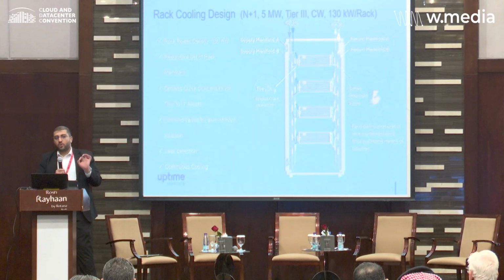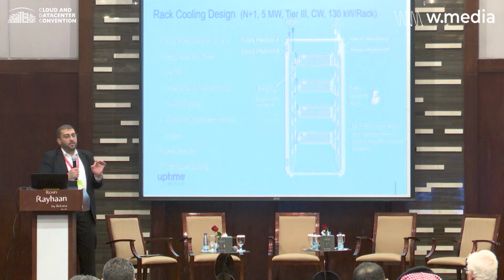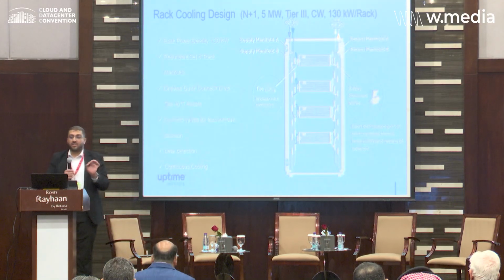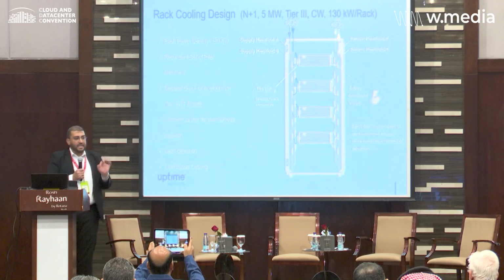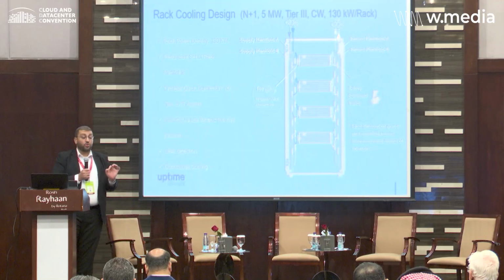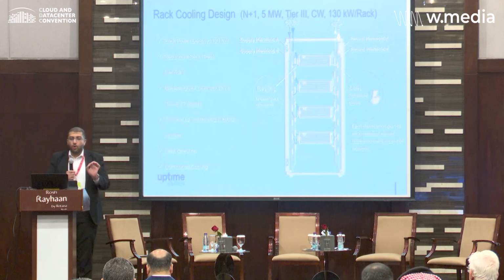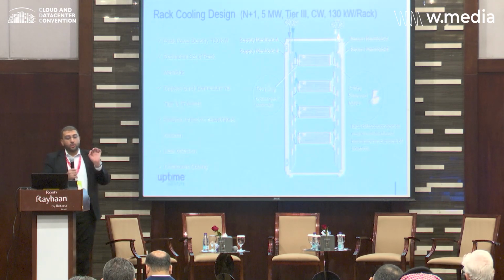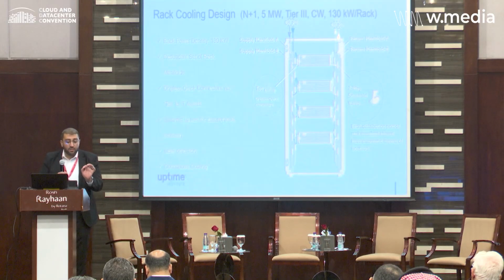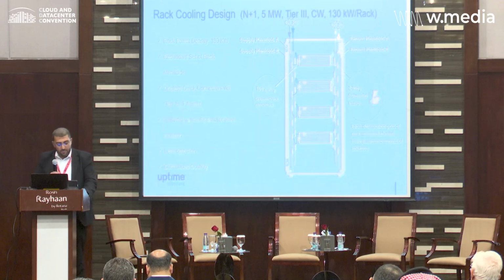Can you imagine the amount of water flow in a 130 kilowatt rack or a 600 kilowatt rack? It's huge. A leak in that manifold can flood the whole data center and can also damage the IT assets. So you need an automation system which protects your IT assets and at the same time sustains your AI workload. That level of reflex and intelligence you need to provide to protect your high-value IT infrastructure. Now, let's talk about how we behave in this world.